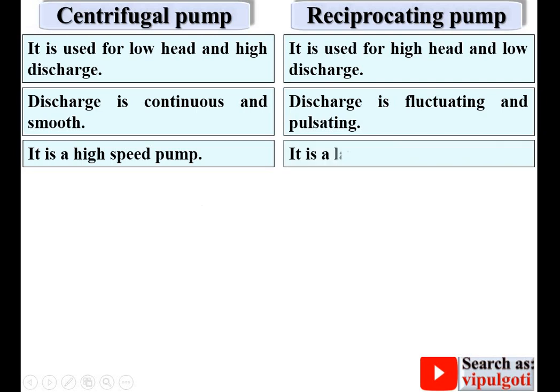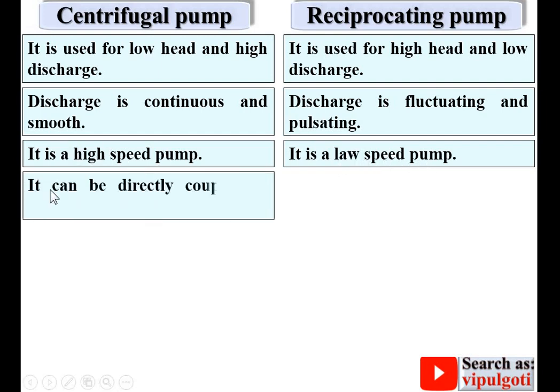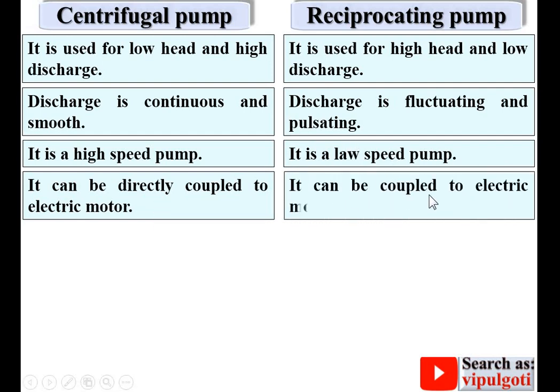Centrifugal pump is a high speed pump, while reciprocating pump is a low speed pump. In the centrifugal pump the impeller rotates, so high speed is possible, whereas in the reciprocating pump the to-and-fro motion means it cannot run at high speed. Due to high speed, the centrifugal pump can be directly coupled to an electric motor, while the reciprocating pump is coupled to the motor through a clutch.